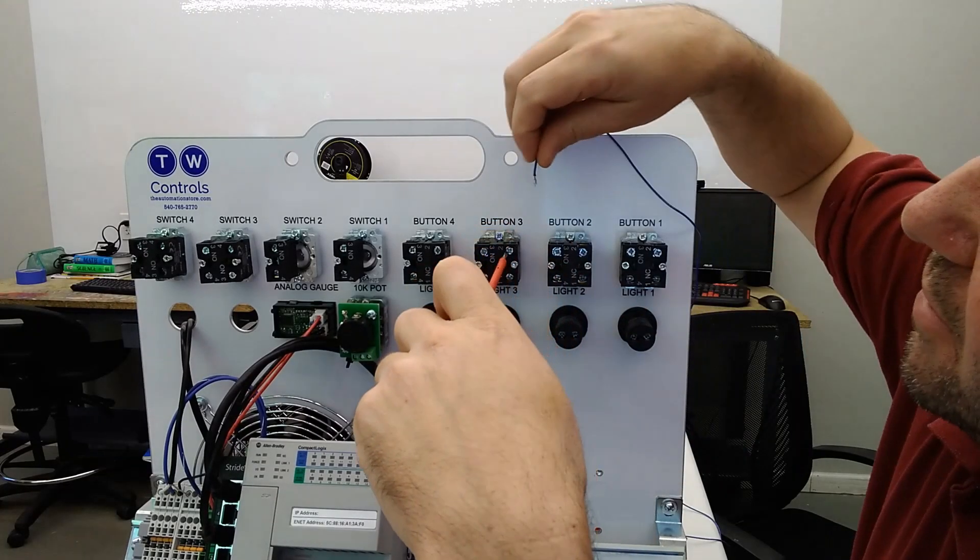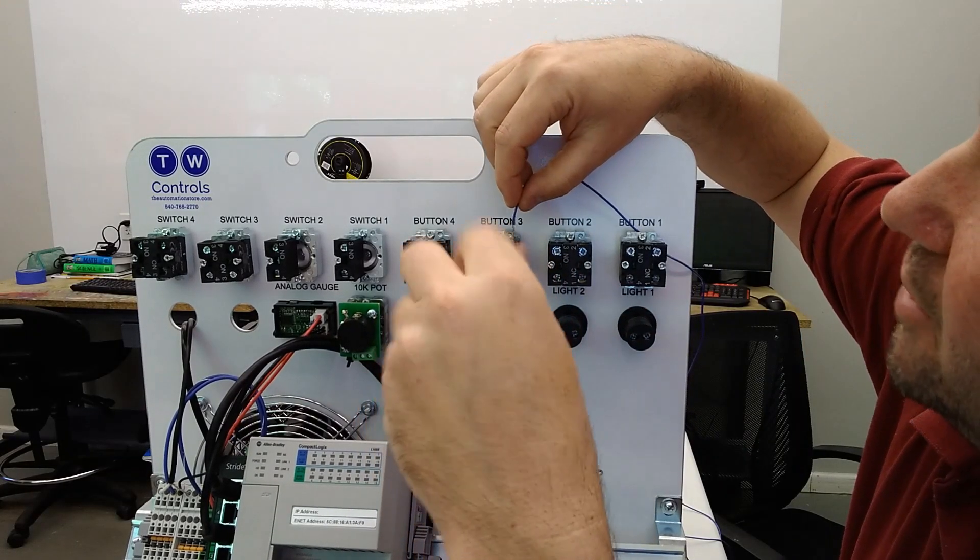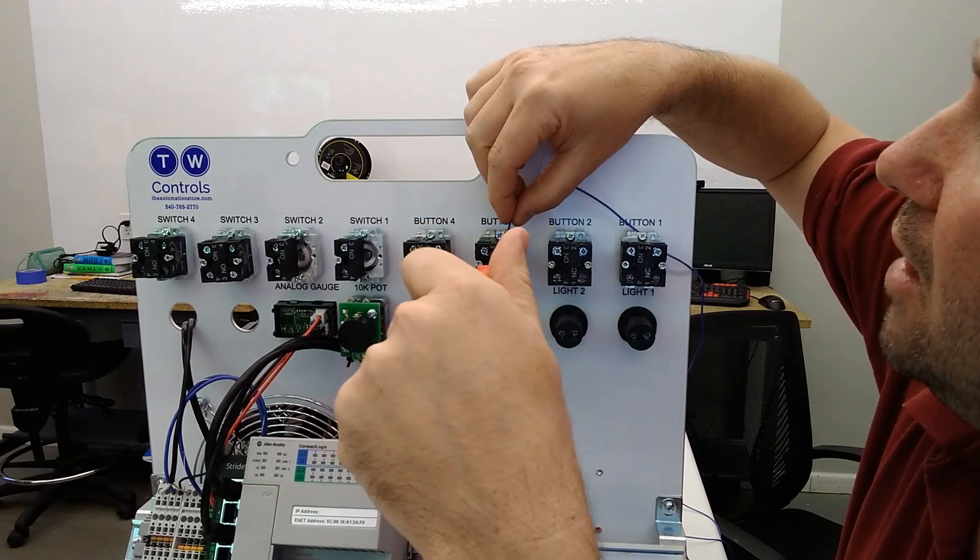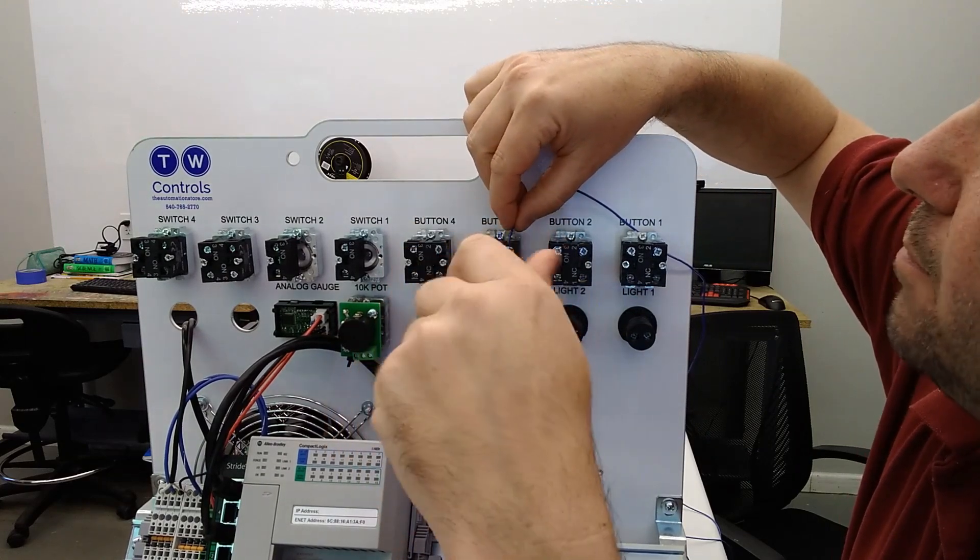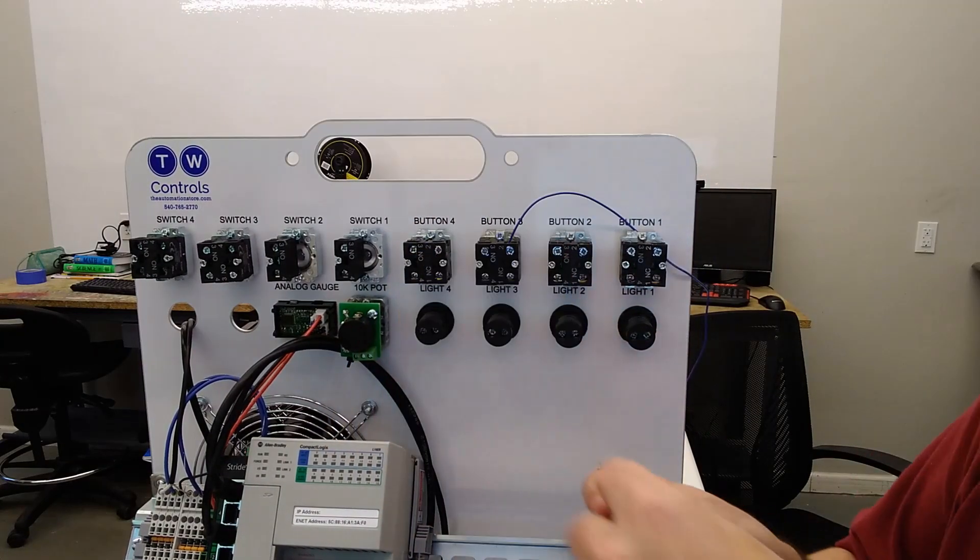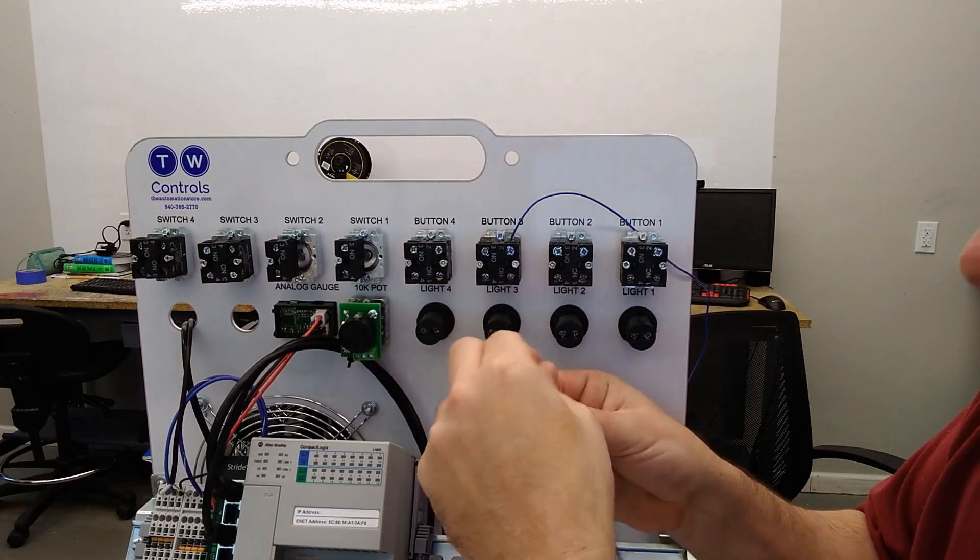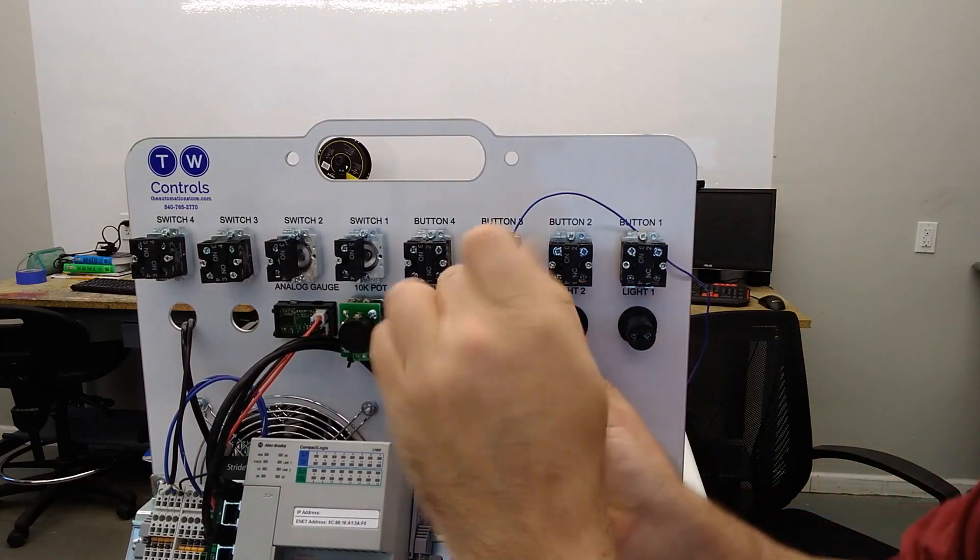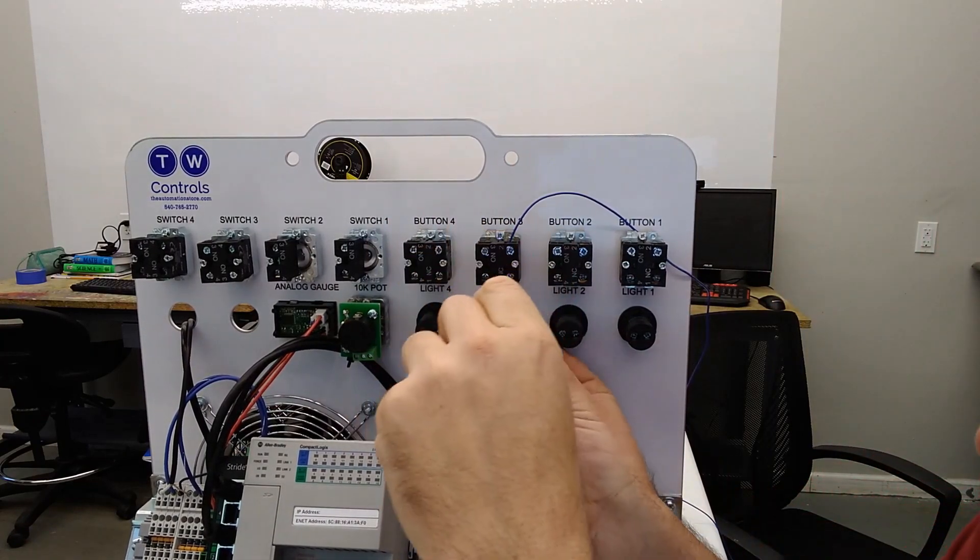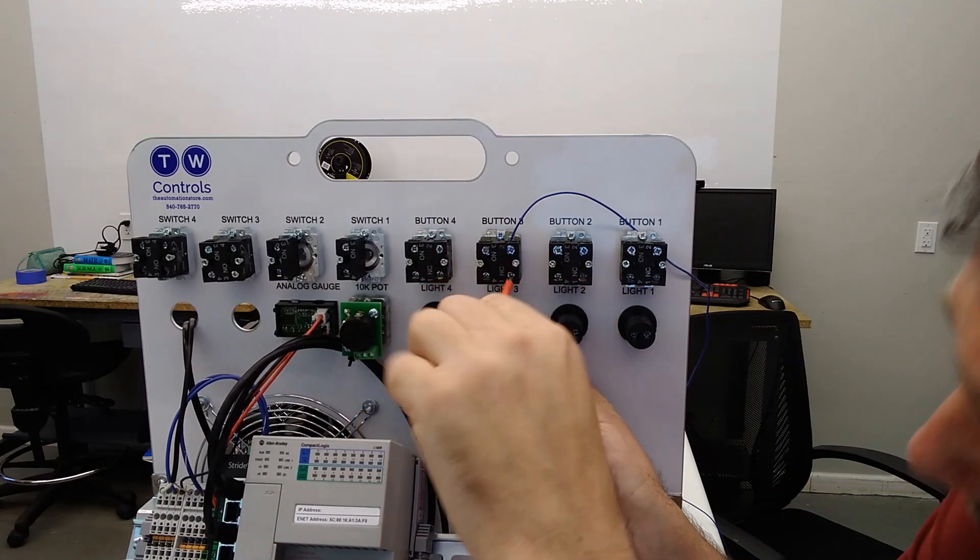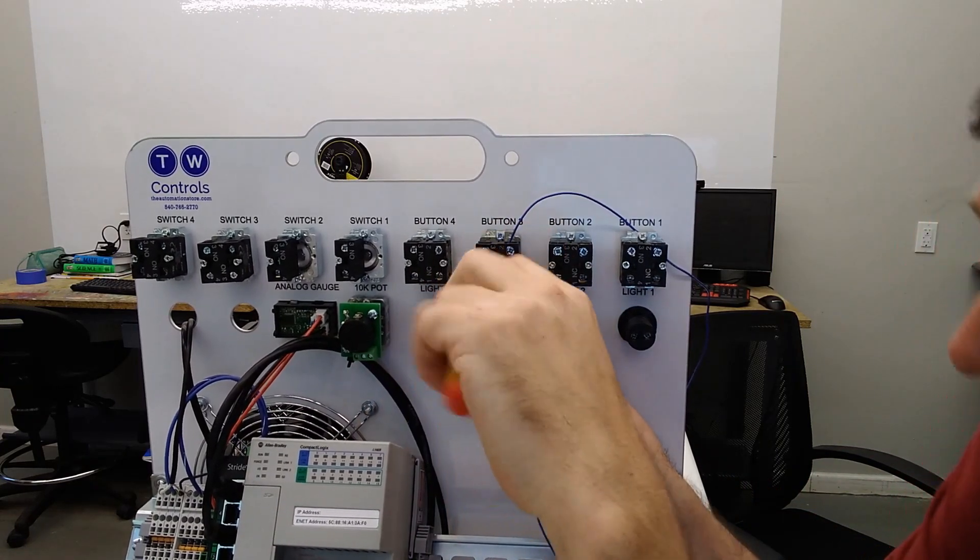Terminal number 11 is going to go to the top side of the normally closed of our red button 3. And then on the bottom side of that normally closed button 3, we're going to put terminal number 1, and we're going to put a jumper wire.